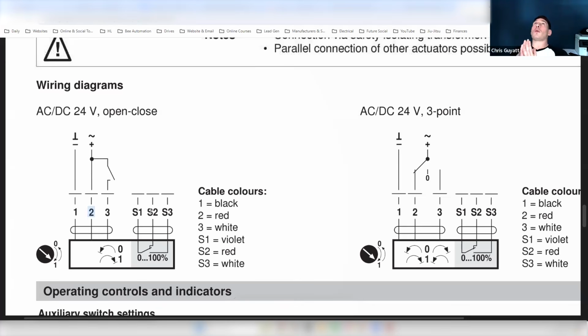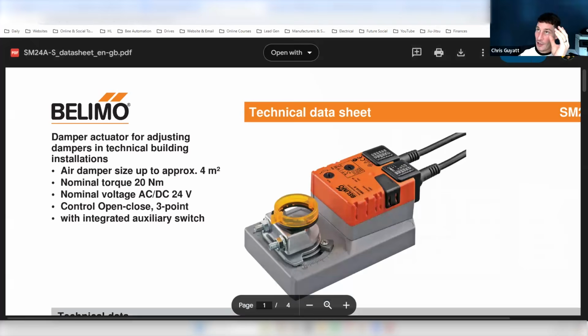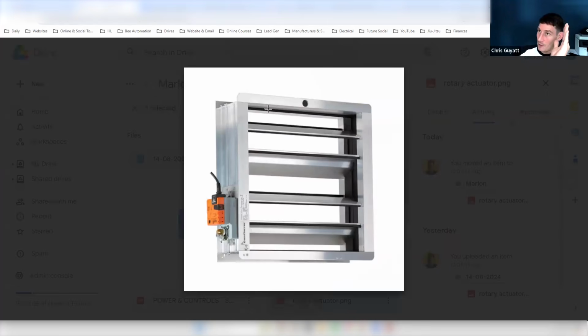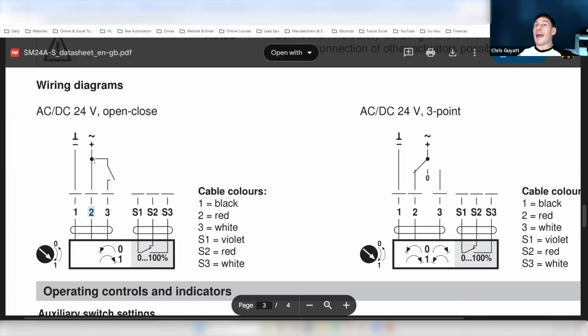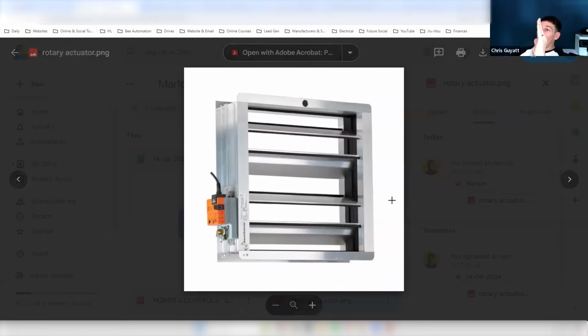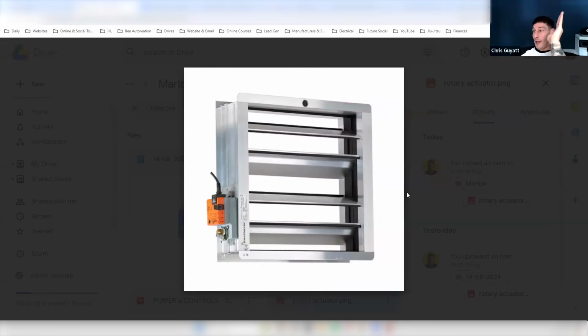So what would be happening now? Let's think about it in terms of the operation. We've got that 24 volts on 2. That would then be closed. We're powering that closed. So it's closed at the moment. And now we've got a little switch here. So this might just be like a relay on a PLC or something, or it could even just be like a switch on the front of a panel. Doesn't really matter. As you can see, we're just closing a circuit here. So currently we've got power going into 2. That's closing the damper. Then if we close this switch here and also apply 24 volts to terminal 3, now what's going to happen is we've gone from closed, now we're going to go open. So as long as we've got that 24 volts applied on 3, that's going to open.